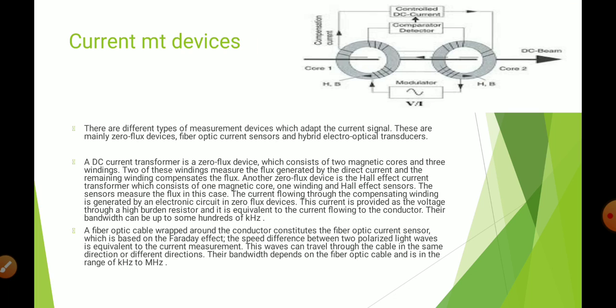A DC current transformer is a zero flux device which consists of two magnetic cores and three windings. Two of these windings measure the flux generated by the direct current, and the remaining winding compensates the flux. Another zero flux device is the Hall effect current transformer, which consists of one magnetic core, one winding, and Hall effect sensors. The sensor measures the flux. In this case, the current flowing through the compensated winding is generated by an electronic circuit. In zero flux devices, this current is provided as a voltage through a high burden resistor and is equivalent to the current flowing through the conductor. Their bandwidth can be up to some hundreds of kilohertz.